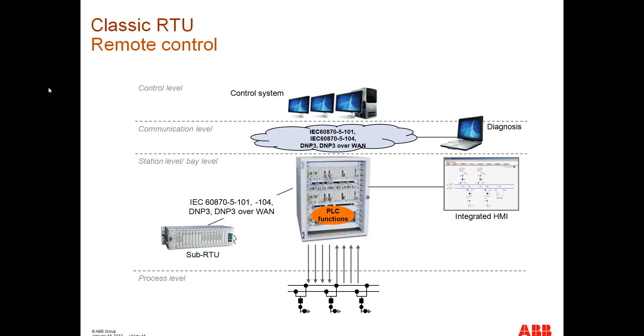And of course there is the possibility to have several RTUs in one station level or bay level to build up a system depending on the process level and the amount of devices in the process level. So let's say one RTU could be server, and the next RTU could then be client and have several IEDs as servers again under the RTU.